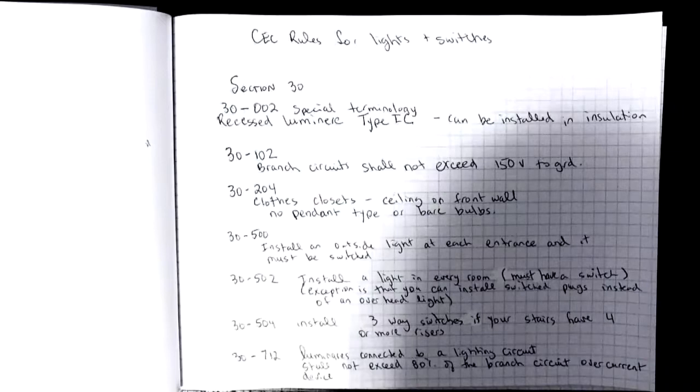30-504 speaks to a set of stairs. If your stairs have four risers or four steps or more, you have to install three-way switches at the top and the bottom of those stairs.